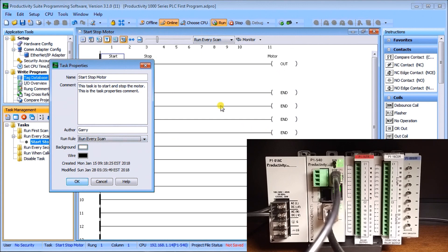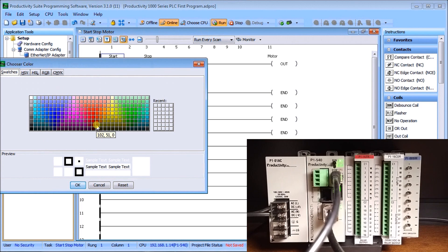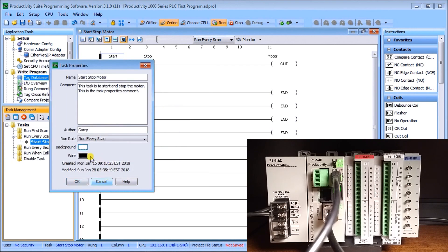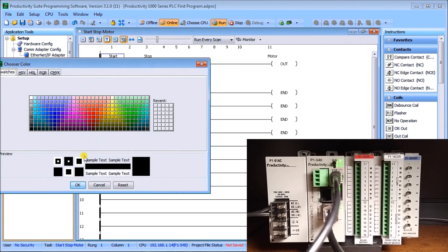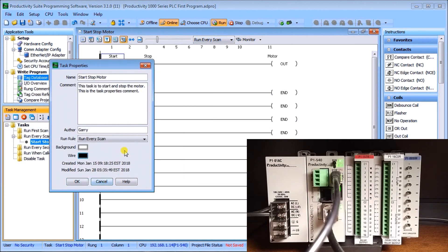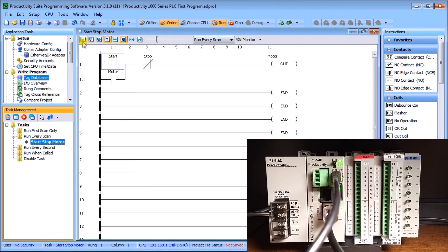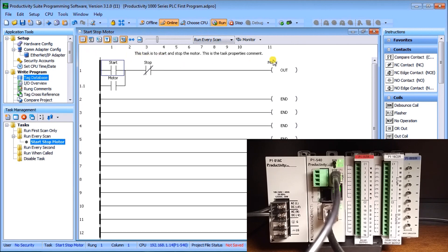Under Task Properties, there's a Run Rule selector — instead of dragging within the task manager you can select it here. We'll leave it at Run Every Scan. There are also Background and Wire color options: Background highlights the entire task, and Wire changes the color of connections between instructions — you can pick any color from a color chart. We'll cancel and leave both as default, then hit OK. Clicking the task comment icon will display the comment in the ladder editor window.